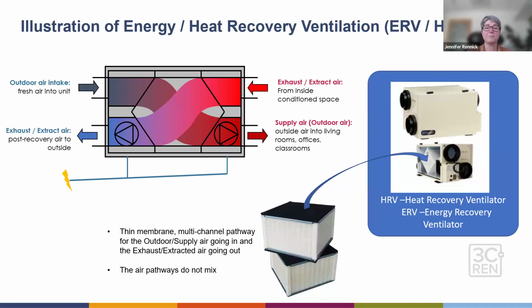But basically, it's a box that holds a core called the ERV or HRV core, filters, and a couple of fan motors. You pull fresh outside air into the box through a duct, and it goes through that core heat exchanger and transfers some of that heat to the outgoing exhaust air that's being pushed out of the building, thereby tempering the supply air that's introduced into the apartment.